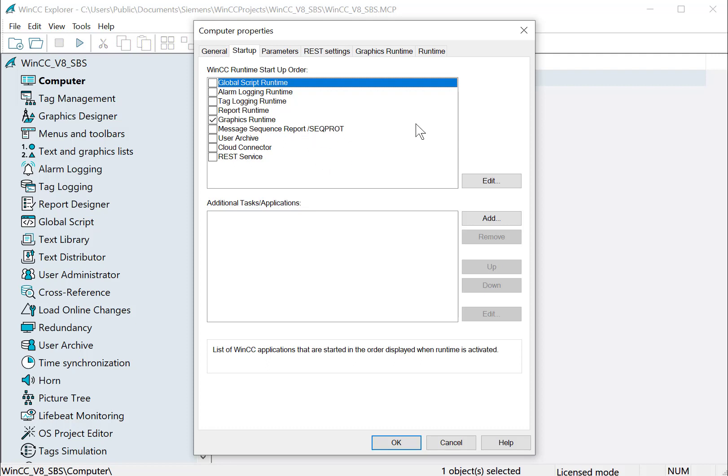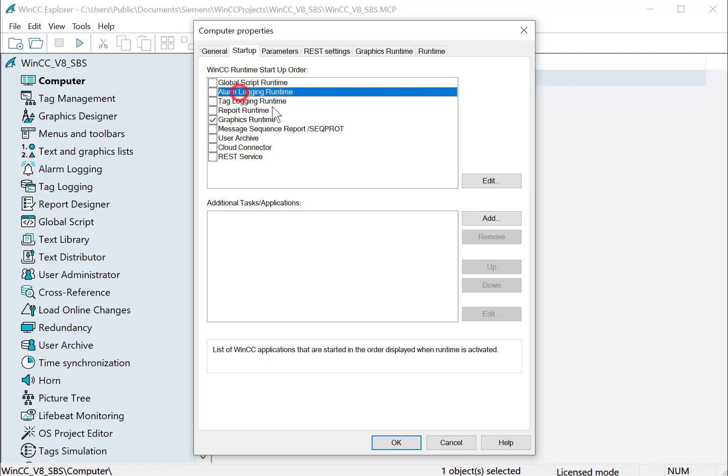But very quickly, under our startup tab, this is where you select the WinCC services that you're running in runtime. So if you configure alarms, you want to come in and turn on alarm logging runtime so it works. Same thing with tag logging, global script, and things like that.